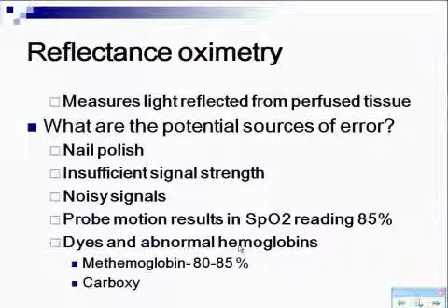Pulse oximeter errors include nail polish and insufficient signal strength, which in other words means it can't measure your pulse, which means you're shocky, and noisy signals. Probe motion results in a saturation reading of 85%, which is just somebody tapping their fingers, which is something that happens a lot in OB. When you're doing OB, women get a little nervous, so they start tapping their fingers when they're awake from the regional, and then you'll start thinking the person's desaturating. All you got to do is tell them calm down, keep your hands still, and then the saturation comes back up to 100%. Usually you can pick it up because when you look at the pulse wave, it's completely erratic. The machine can't measure that. So it's a great machine when a person's asleep. The more a person moves, the more artifact there is, the more problems with it.